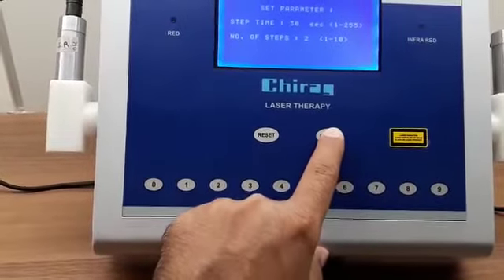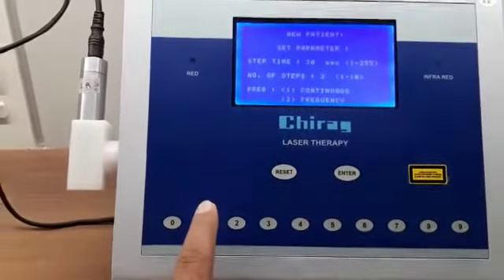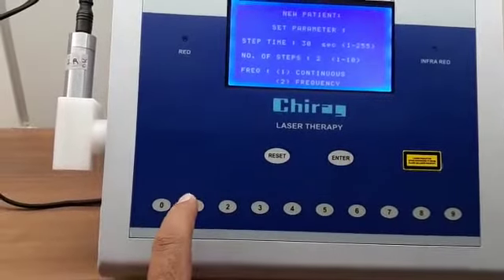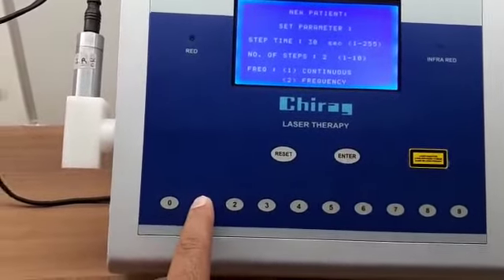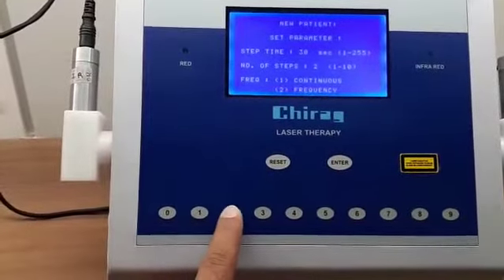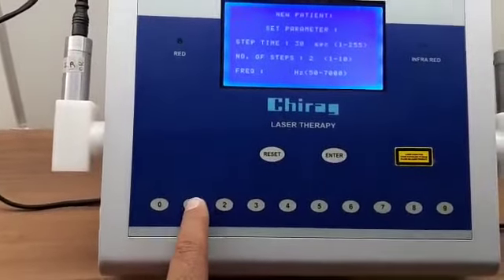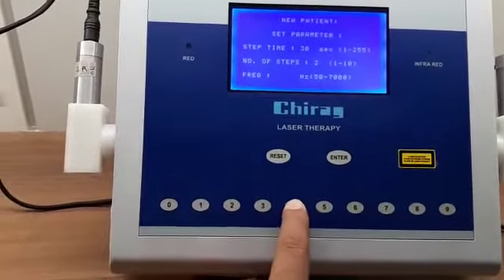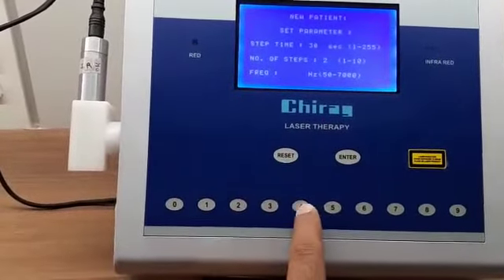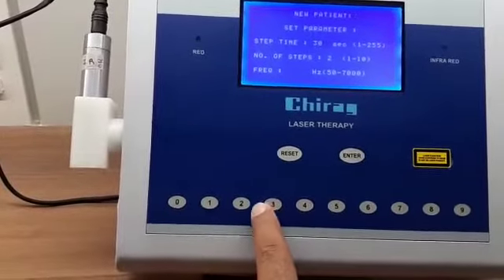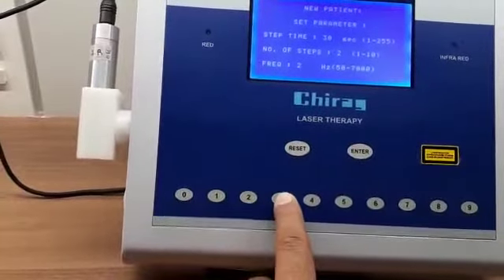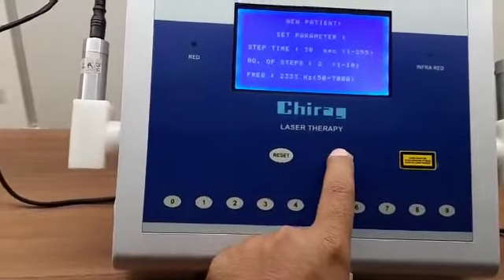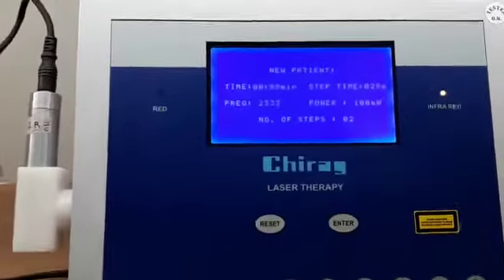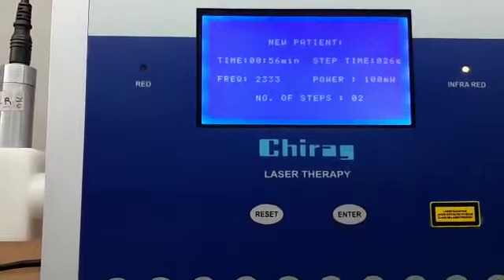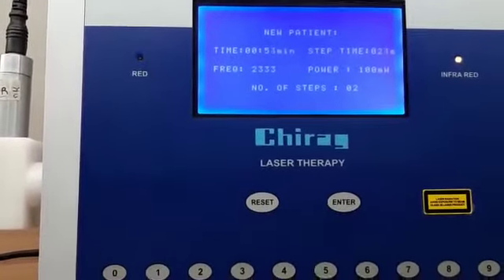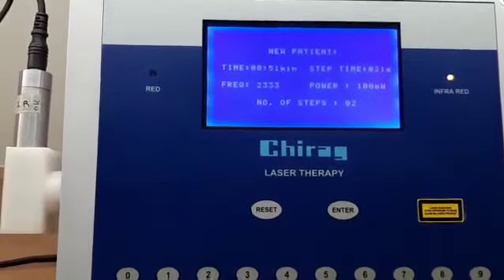Total treatment time would be 60 seconds, 1 minute. Continuous frequency will give more power. If you go for frequency mode, the power is altered, the power is chopped, and the output is in pulses. Let us have any combination from 50 to 7000 Hz. For example, 2, 3, 3, 3. Enter. So now treatment time was 60 seconds and it is decreasing. The frequency is 2333 Hz, power is 100 milliwatts fixed, number of steps is 2.